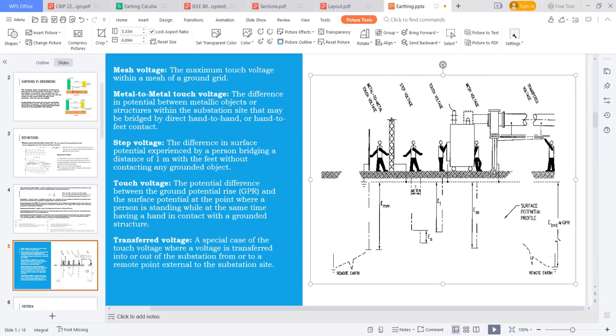These are the three cases where a person can feel and experience. Generally, what you will do in a substation — either you walk, or you touch some equipment. So if you are touching any equipment, a voltage will develop across your body to the ground. That could be a touch voltage. Or else a person is not touching anything and is walking — when he is walking, a potential may develop between his two legs by bridging a distance of one meter without touching any object. So these are the main two voltages we can experience.